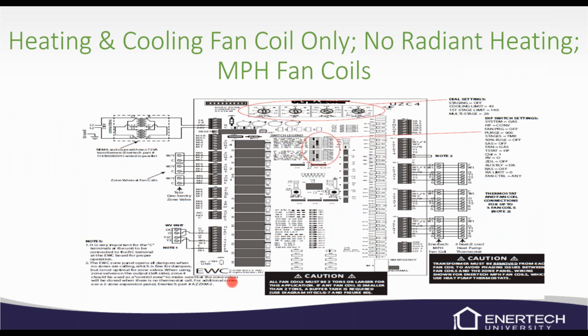This is using MPH fan coils with no radiant heat. This is the EWC zone panel. Some of you may be familiar with it from doing ducted zoning, but as you can see, we've got 4 zones here. Well, this 4th one up here, you can see we've just got a little jumper between R and G, and that's to give it that dummy call. If you need more than 3, then you're going to have to get another expansion module for this EWC, which is available. Make sure we're always setting up the dip switches, and if you've got an expansion module, make sure it matches the settings that you have on your first EWC module there.